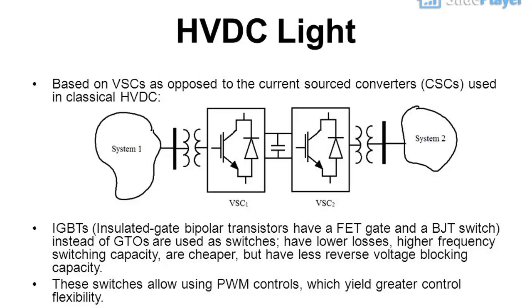HVDC Light: based on VSCs as opposed to the current sourced converters used in classical HVDC. IGBTs (insulated gate bipolar transistors) — which have a FET gate and a BJT switch — are used instead of GTOs as switches. IGBTs have lower losses, higher frequency switching capacity, and are cheaper, but have less reverse voltage blocking capacity. These switches allow using PWM controls, which yield greater control flexibility.